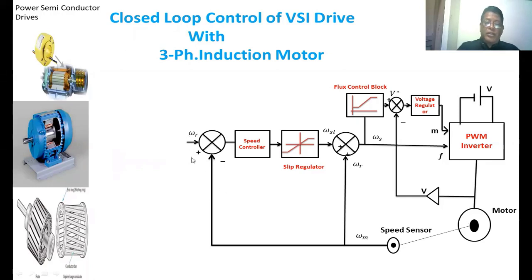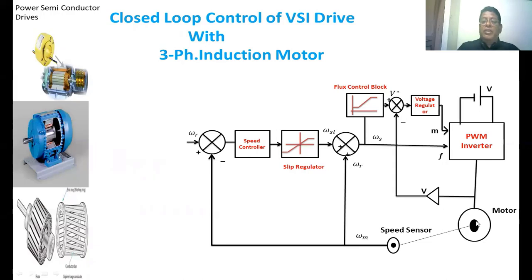Suppose there is a decrease in reference speed — the error in speed becomes negative, which sets the slip regulator to a negative slip speed. Whenever the negative slip speed is set, braking of the induction motor occurs at maximum torque condition. Negative slip speed corresponds to the braking operation, so the speed of the motor decreases. Once the speed decreases, the error in speed decreases. Finally, the slip of the induction motor is set to a value such that the developed torque equals the load on the induction motor.